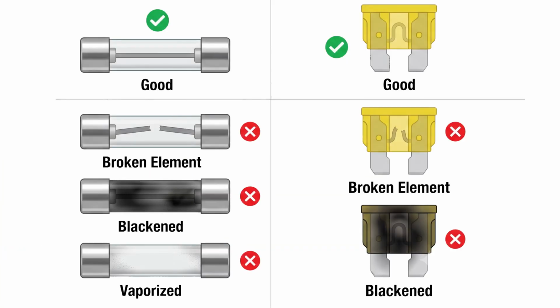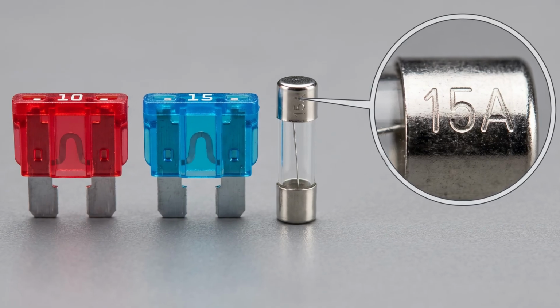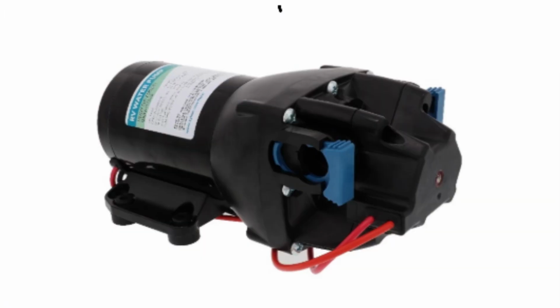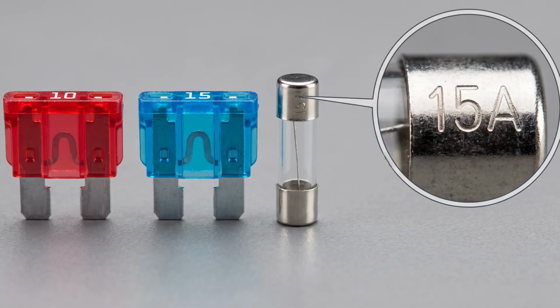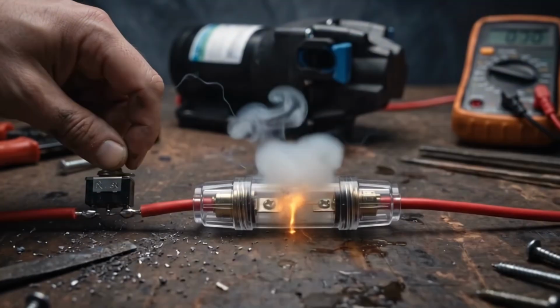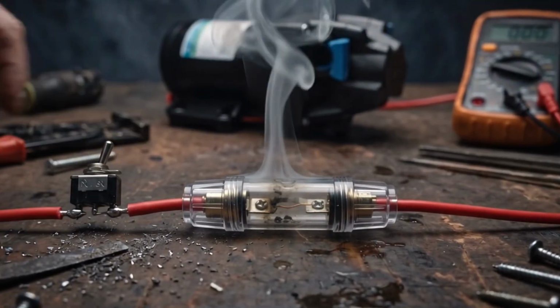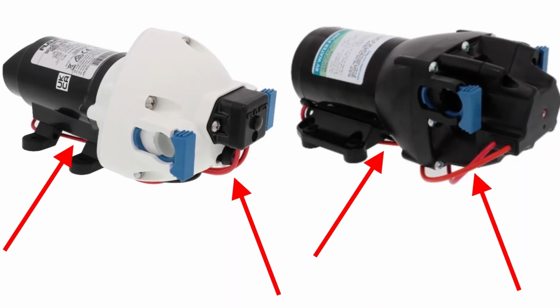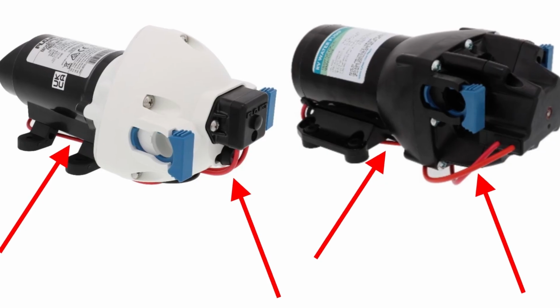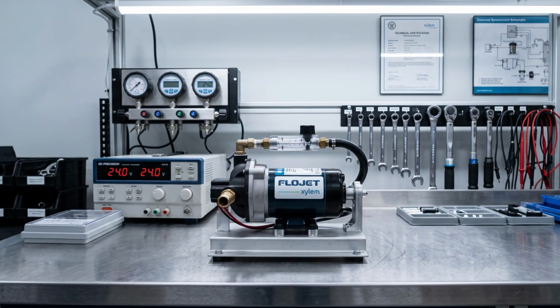Pull the fuse out. Look closely at the thin metal filament inside. If that wire is broken, blackened, or missing, the fuse is blown. Replace it only with the exact amperage rating specified on your pump's product label, typically a 10 amp or 15 amp fuse. If a brand new fuse blows instantly the second you turn the power back on, inspect the visible wiring for short circuits. If you can't find any damage, the pump must be professionally serviced.